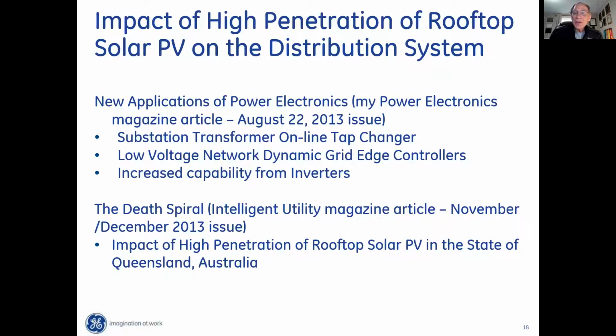What happened was, in the substation there's an online tap changer. Its job is, no matter how the primary voltage fluctuates, it keeps the secondary voltage constant, because you want the voltage at your home to be constant. Otherwise your light bulbs would go very bright, very dim, as the secondary voltage changed. The tap changer is a mechanical controller with 16 raise positions, 16 lower positions, and a neutral position, changing to keep the secondary voltage constant as the primary voltage fluctuates. The more volatility in the primary voltage, the more times the tap changer operates, and the more it operates, the more its life decreases. It's mechanical, so it wears out.